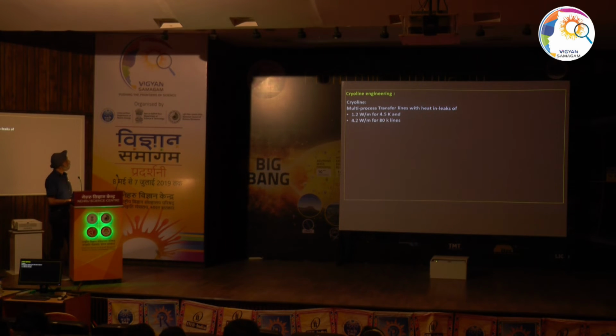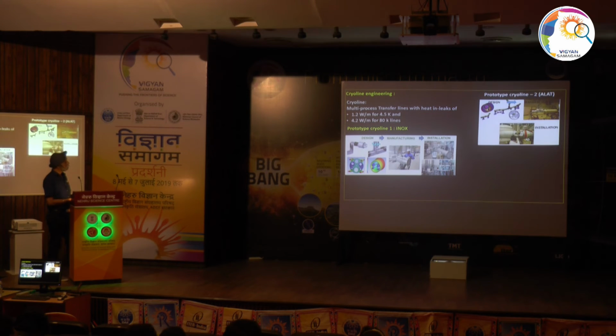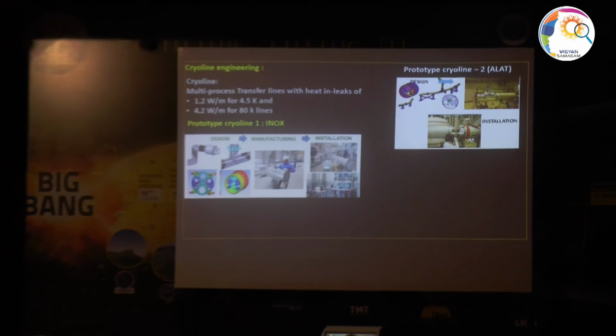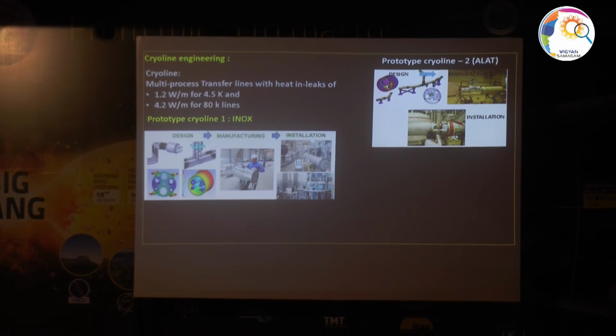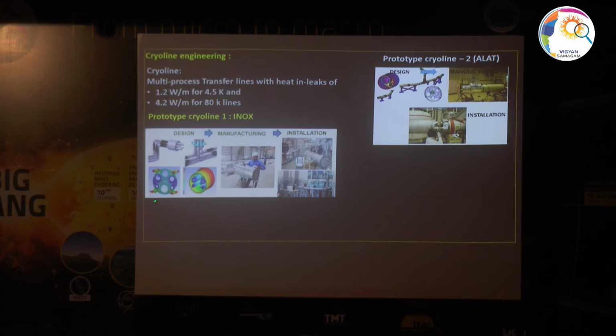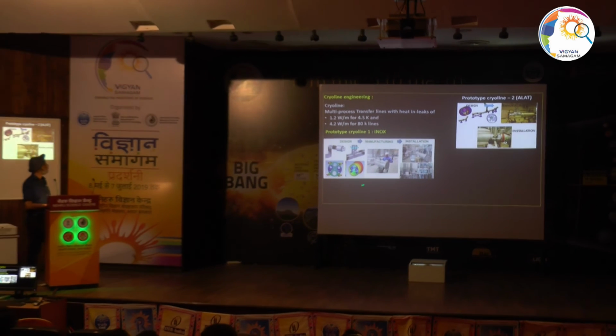Now let us come to the cryo lines. The requirement is that for the 4.5K lines, heat in-leaks should not exceed 1.2 watts per meter, and for the 80K lines, not more than 4.2 watts per meter. In India, while developing SST, we had also developed transfer lines with multi-layer insulation, but those were single transfer lines. Here the requirement is an assembly of transfer lines in a single jacket.